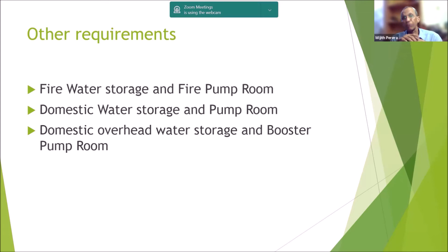Then the domestic water storage. It can be underground, it can be above ground with a small underground tank, because our municipality water supplies do not have sufficient power to pump up to even 3-4 story buildings, and you are not allowed to directly connect the pump and boost the water flow. You have to always have an underground sump into which the service connection will be connected, and then from the sump you need booster pumps. It can be either at ground level and boost the water supply to all the floors, or a better system is to have a small booster pump at the rooftop level, which will only be necessary for the 2 to 3 topmost floors, and use the gravity head to boost the pressure of other floors. But these also need to be accommodated.